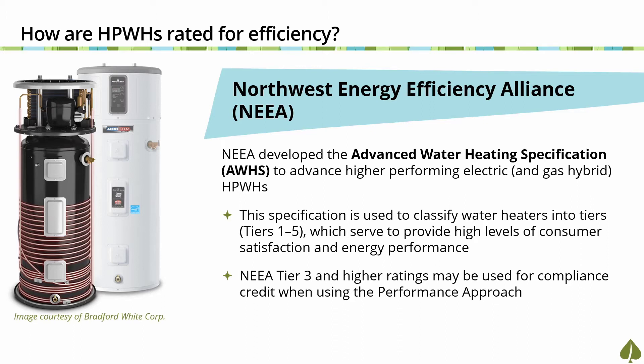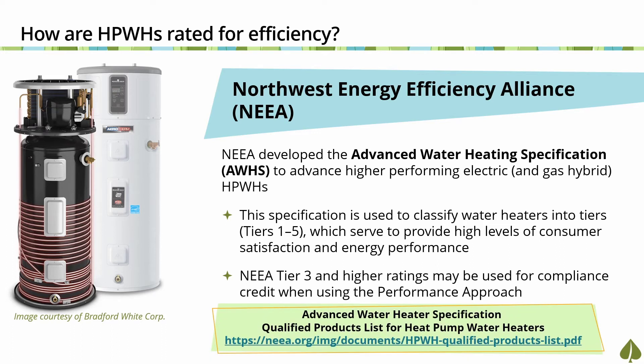The NEEA Tier 3 heat pump water heater specification includes improved features such as minimum cool climate efficiency, or CCE, Energy Star compliance, a 10-year warranty, intake and exhaust ducting capability, and lower sound levels when the equipment is operating. Using a NEEA Tier 3 heat pump water heater may be used for a compliance credit when using the performance approach. A list of AWHS qualified products is available through the neea.org website.